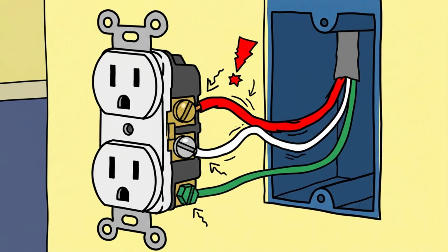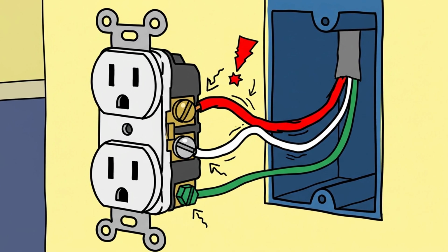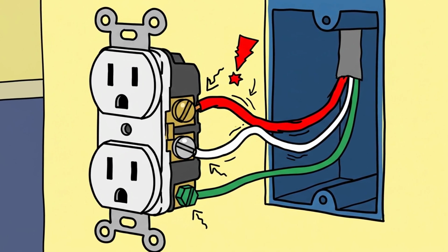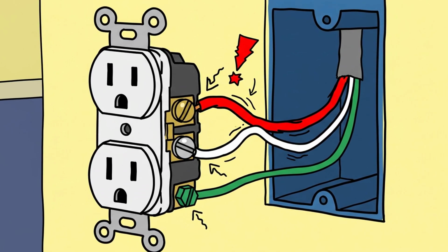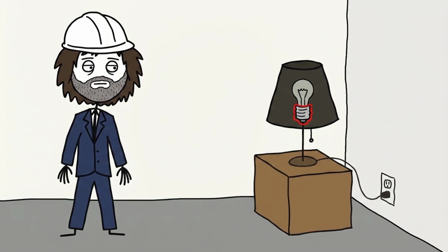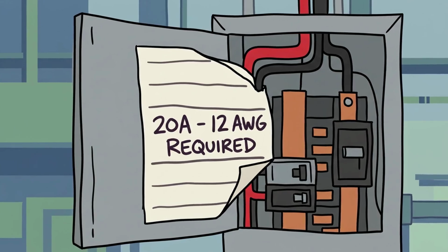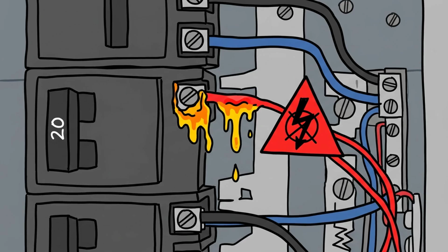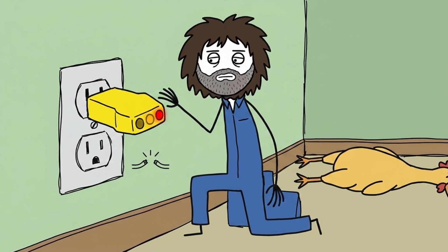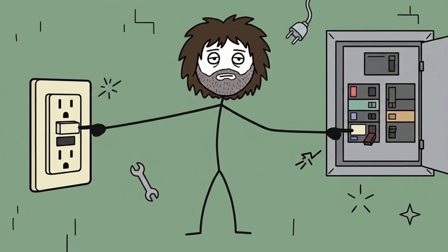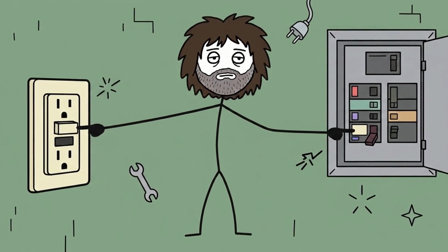A GFCI breaker continuously monitors current flowing out on hot versus returning on neutral using an internal differential current transformer. Under normal conditions, every electron leaving the hot wire must return through neutral. However, if a person touches a frayed cord while standing on a wet floor, a tiny fraction of current leaks through their body into ground instead of neutral.